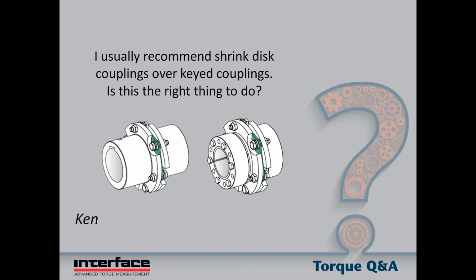The next question is, I usually recommend shrink disc couplings over keyed couplings. Is this the right thing to do? I agree. We recommend shrink disc type couplings, which basically is any type of coupling that grips the shaft as opposed to a keyed connection. Most of the sensors that we sell actually do have smooth shafts, and the keyed shafts are an option. There's a couple of reasons for that. One is a gripping type coupling, or a shrink type coupling, applies the torque evenly around the perimeter of the shaft as opposed to a point load at the key.